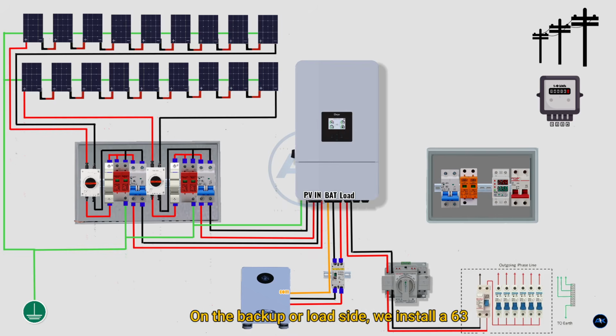On the backup or load side, we install a 63 amp AC breaker to protect the inverter's output circuit. From the breaker, the load wiring goes to the essential load subpanel or ATS, depending on how the system is configured. This ensures stable and protected power delivery to critical home circuits during both grid and solar operation.